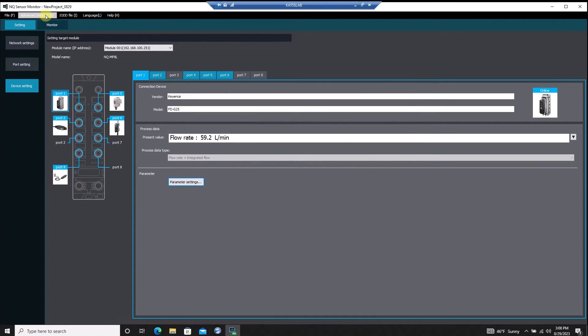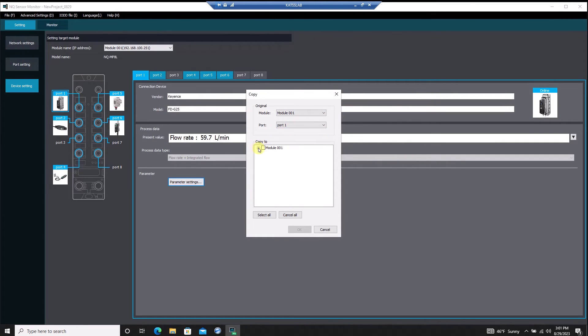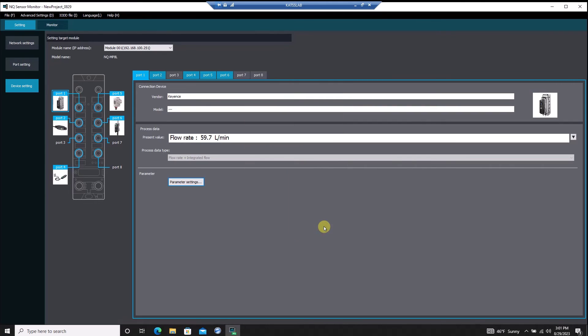Once you've got a device configured, you can easily copy the settings from that device's port and paste the settings to another port, allowing the ability to set up IO-Link sensors in large batches.